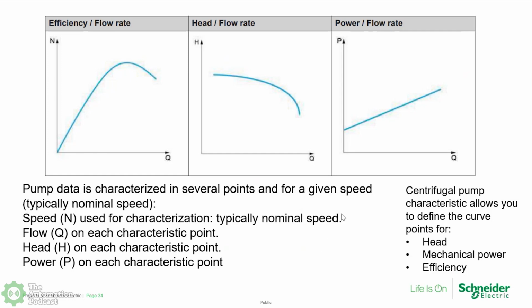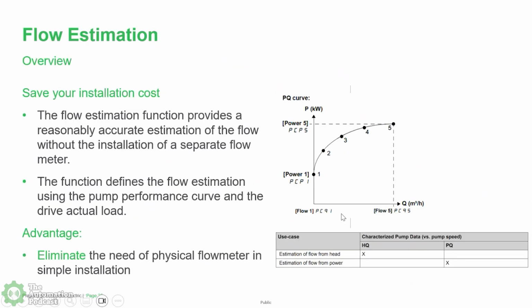And as long as we plug in that pump curve, we can actually create a flow estimation based off of that. So we add our 5 points from the pump curve, program them onto the VFD, and it'll create a reasonably accurate flow estimation of what the pump is doing. This completely eliminates the need for a flow meter.